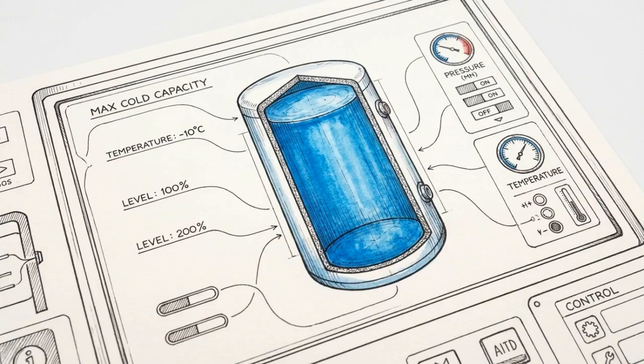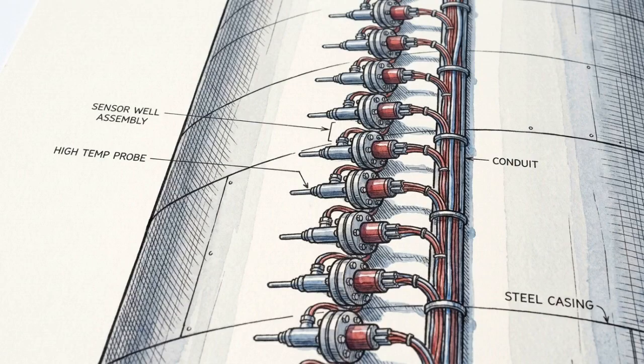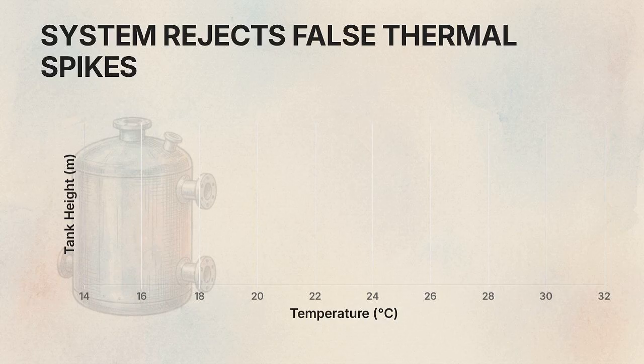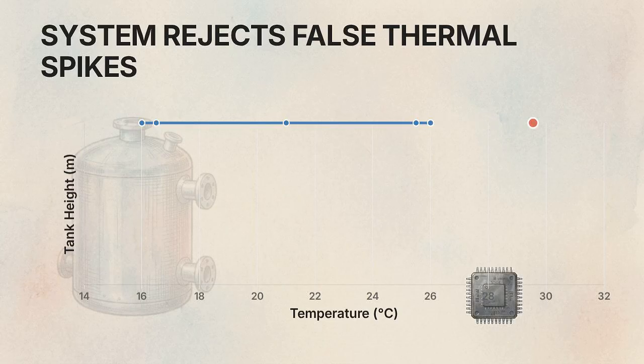In operation, the system determines its exact state of charge by integrating data from a vertical array of temperature sensors mounted along the height of the tank. A credible state of charge calculation depends on the entire validated vertical profile. The control logic is programmed to reject impossible temperature gradients or single sensor jumps that could falsely report readiness.